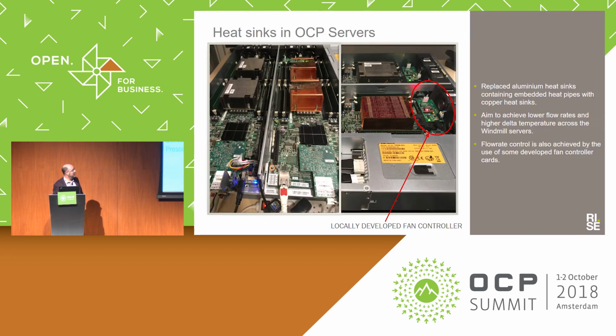And to do that with this OCP hardware, we've created a small control card, just here. What you can see is a small card that sits in between where the fans were connected to the motherboard—it interrupts that—and through some mechanism through the OCP hardware, we can take control of the fans, and therefore dial in a flow rate we want across the server for a target delta T.